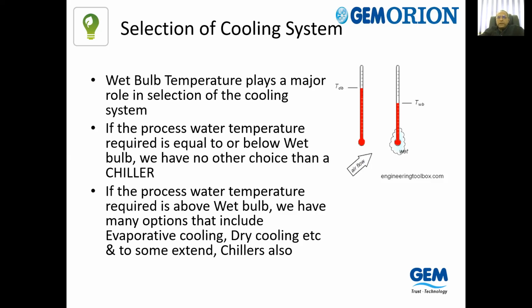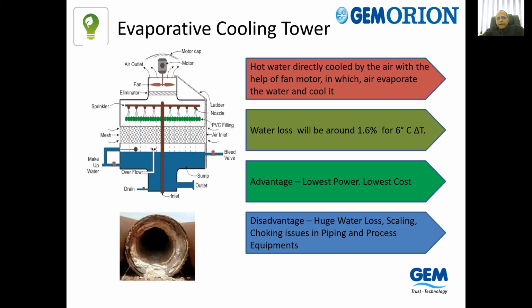So whenever the required process temperature is above the wet bulb temperature, a simple cooling tower system with evaporative cooling can work. But for any process that requires temperature below the wet bulb temperature, chillers are the only solution. So this is a typical cooling tower installation where we have a lot of evaporation taking place. Even if you use good quality water, during evaporation the pure H2O will evaporate and the remaining salt will continue to accumulate in the water. So you have to do continuous blowdown.